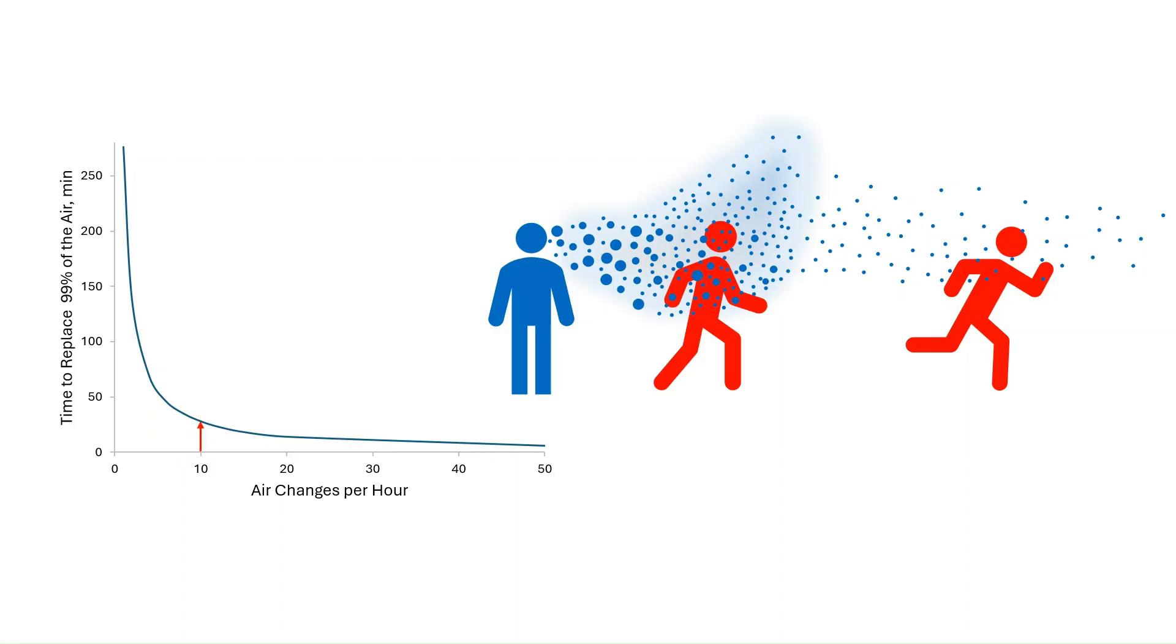Increasing the ACH from 4 to 10 drops this time even further, down to 28 minutes. This more than doubling of the ACH leads to about a halving of the time taken to replace the air. If the ACH is increased from 10 all the way to 50, the time will drop but not as dramatically. This means that after a certain point, the payoff from increasing the ACH is just not as significant.